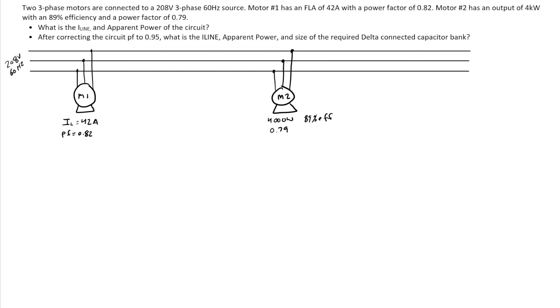So what we want to do here is we want to calculate the I-line and the total apparent power of the circuit. And then we want to correct the entire circuit to 0.95 power factor. Calculate again the I-line, the apparent power, and the size of the required delta capacitor bank.